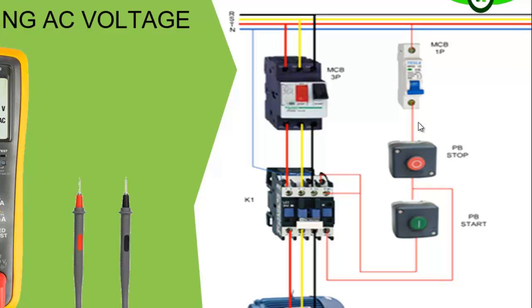So now, remember, we have tested to the output of this circuit breaker feeding this control circuit. Let's assume that this one is okay. Then to the input to your stop button, okay, if you test, if it is okay, it means that we have power to this your stop button. So remember, the stop button is a normally closed push button. Normally closed push button. Okay. So what is sure is that since it is normally closed, you are supposed to have voltage signal at the other end, the output of that normally closed push button.